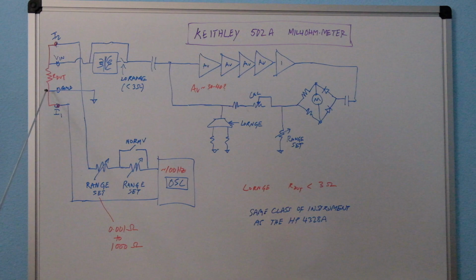And the AC voltage that is developed across this DUT is then, in the case it's done in low range mode, less than 3 ohms, there's a transformer that is in circuit. And if you're going in the higher resistance mode, you don't need a transformer, you just bypass it and AC couple, and then this amplifier chain amplifies by around 120 dB by my estimation, because these amplifiers are fairly high gain, GM times the plate resistance is around 2 mega ohms. So I would say each of these stages has a gain of around 30 or so, and so 30 raised to the power 4 is in the hundreds of thousands.